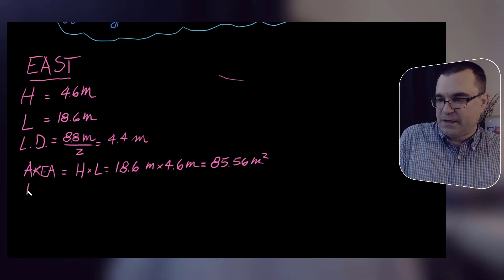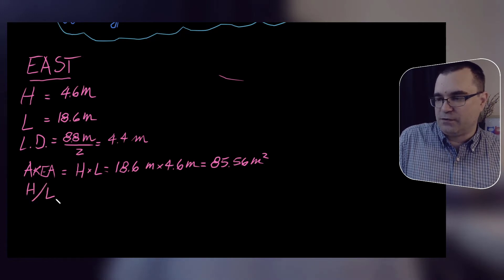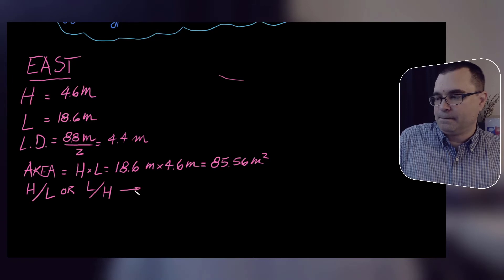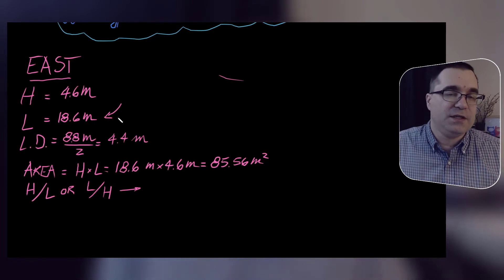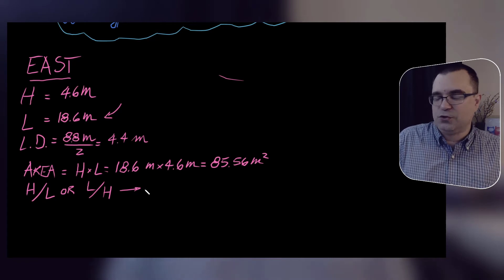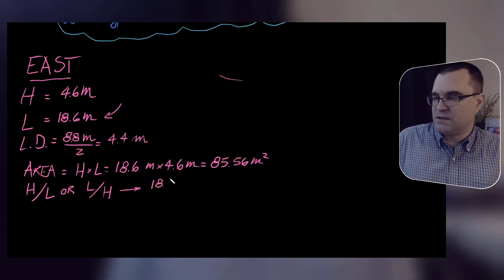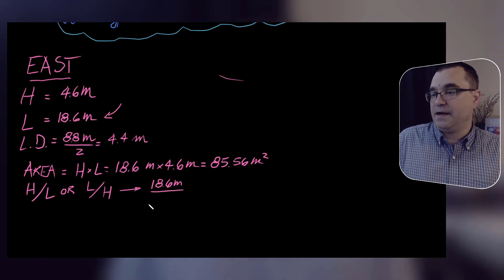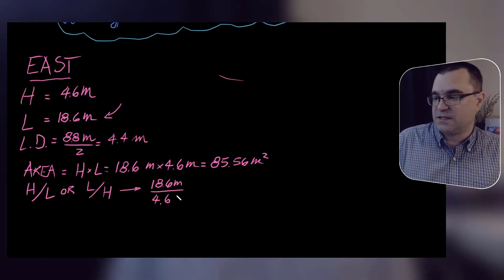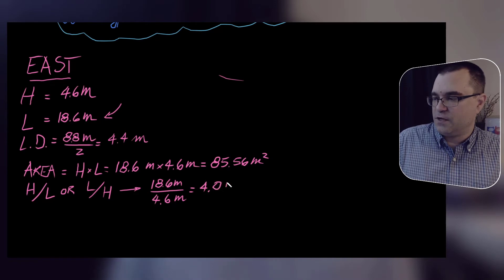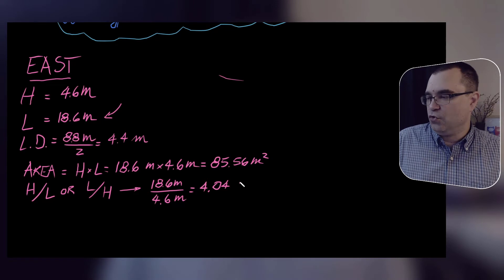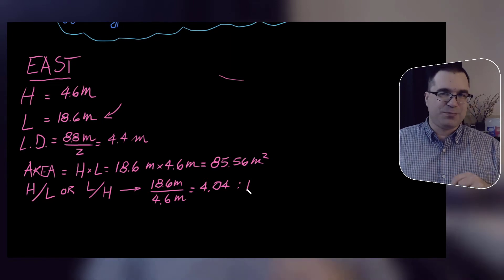We also have to figure out H over L and L over H and take the larger one. Since L is the larger of the two values, L over H is going to be larger than H over L. So I'm going to do L over H: 18.6 divided by 4.6, which gives us 4.04 — the same as writing 4.04 to 1 — so that we compare it against the proper row in the table.